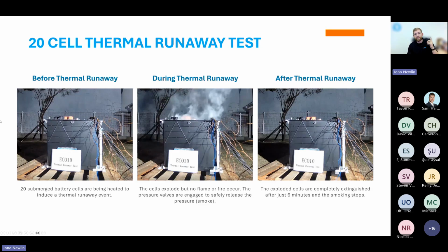Here we triggered 20 cells at one time. This was before the thermal runaway, and this was during and after. No flame was present—all you see at the peak is gases being emitted out of the module, with no flame throughout all 20 cells being triggered at once. In the aftermath, the system or module remained well intact, able to contain that thermal runaway, let it run its course, dissipate the energy, cool down, and become inert.